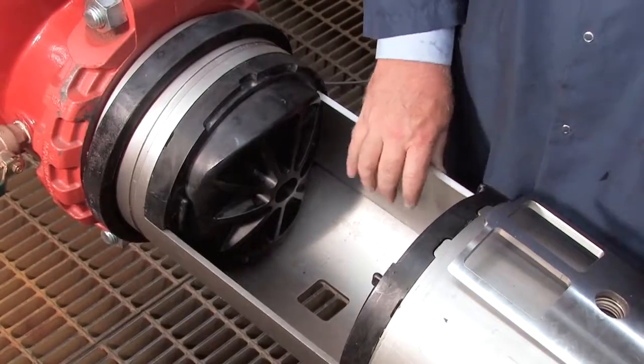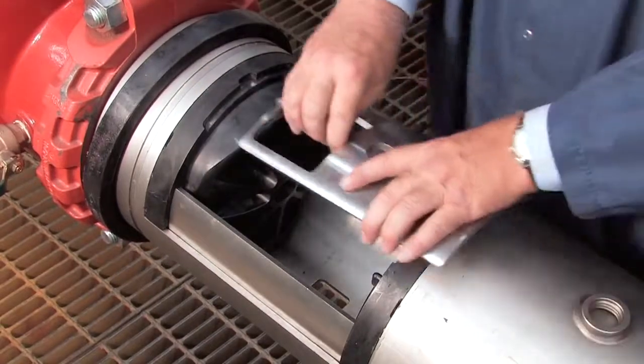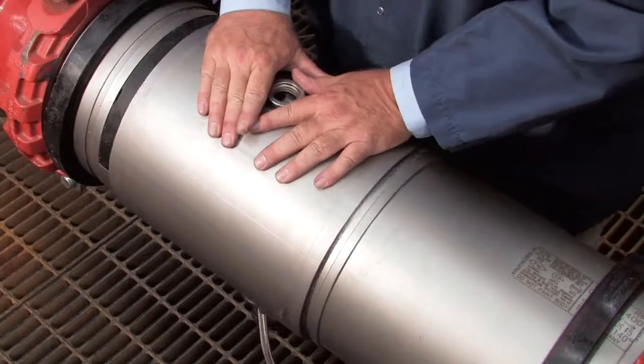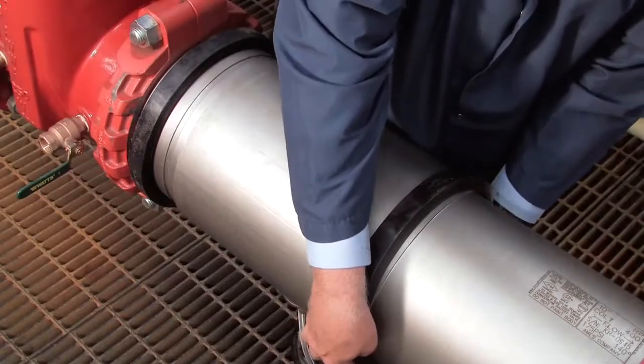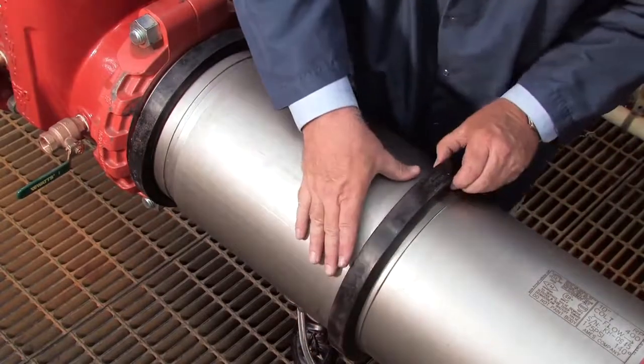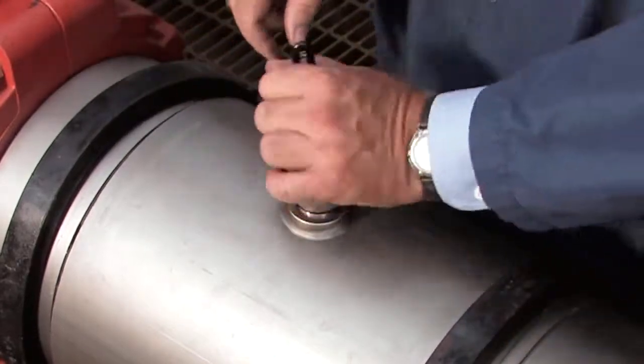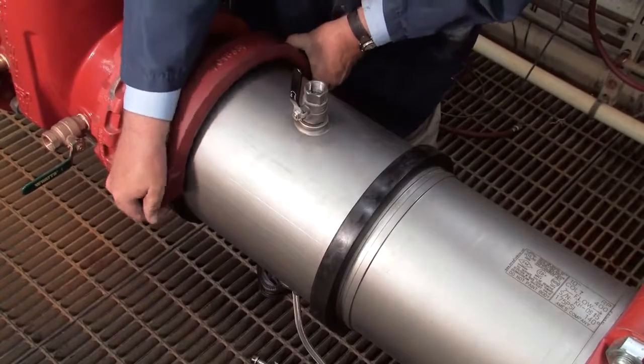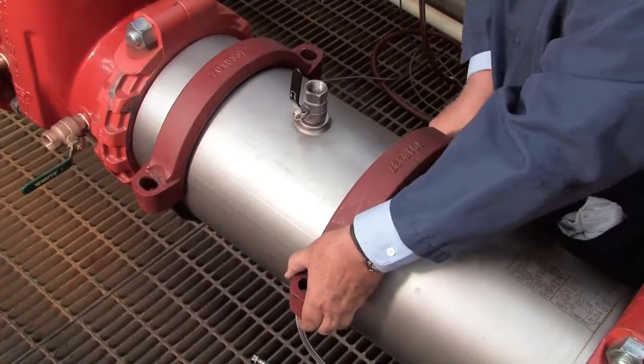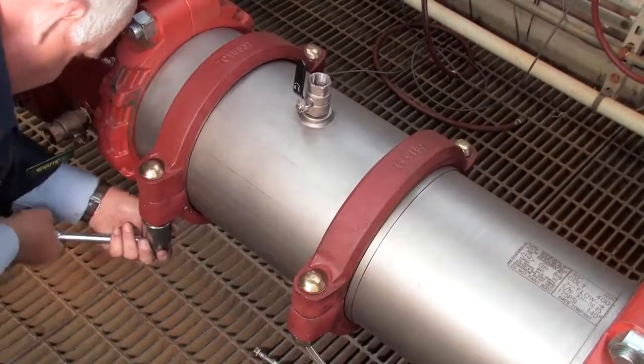With the checks replaced, reinstall the stainless steel retainer plates and close the cover sleeve. Replace the rubber gaskets around either edge of the sleeve and re-thread the number 3 test cock. Finish rebuilding the assembly by reinstalling the two couplings around the valve body. Tighten the bolts evenly until they make pad-to-pad contact.